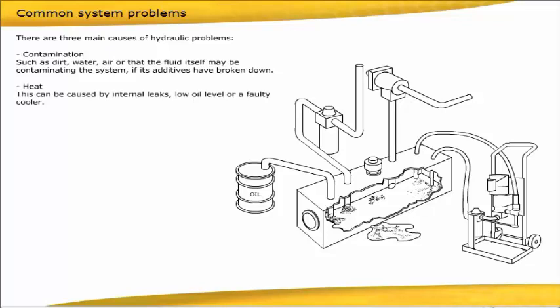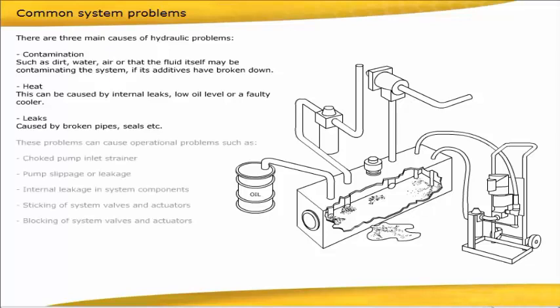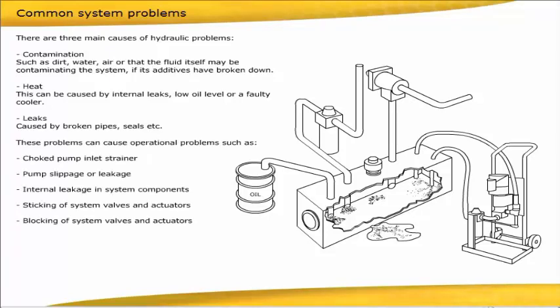This can be caused by internal leaks, low oil level or a faulty cooler. These problems can cause operational problems such as choked pump inlet strainer, pump slippage or leakage, internal leakage in system components, sticking of system valves and actuators, blocking of system valves and actuators.